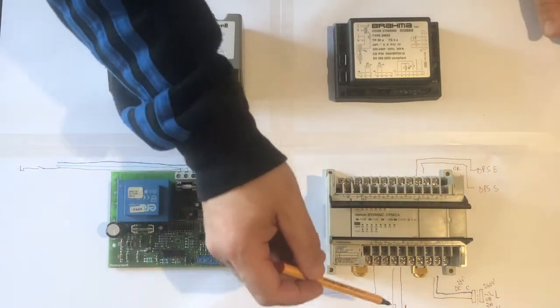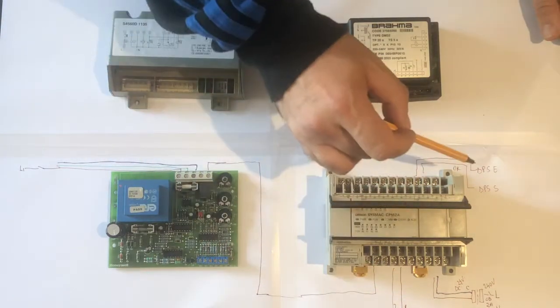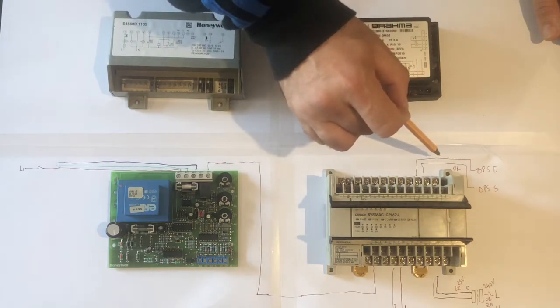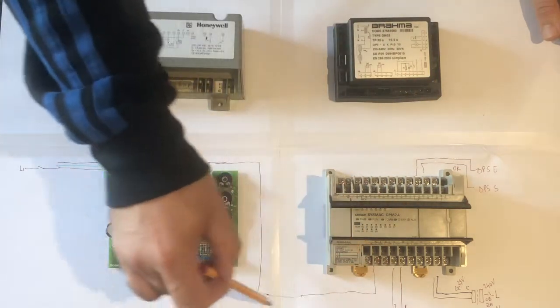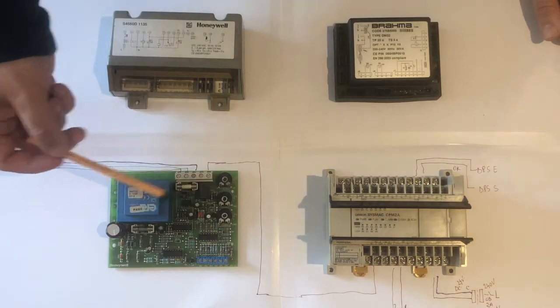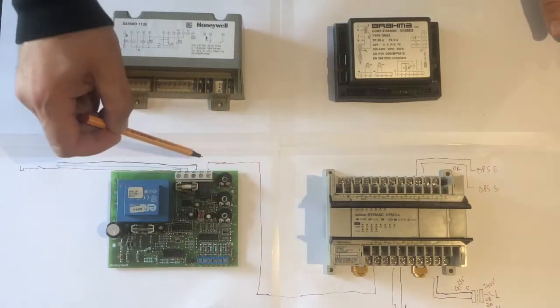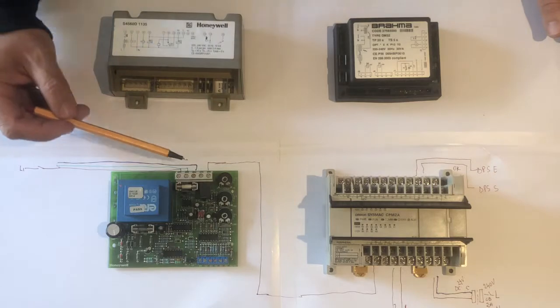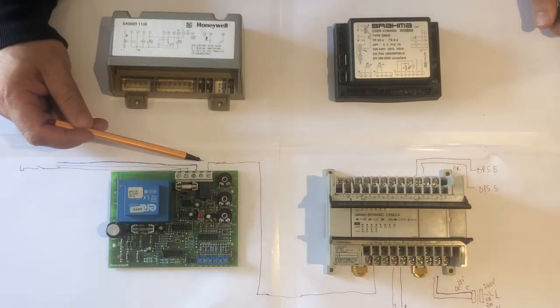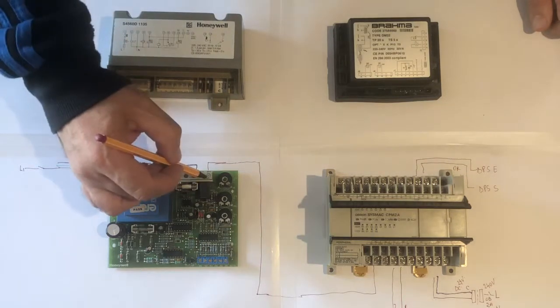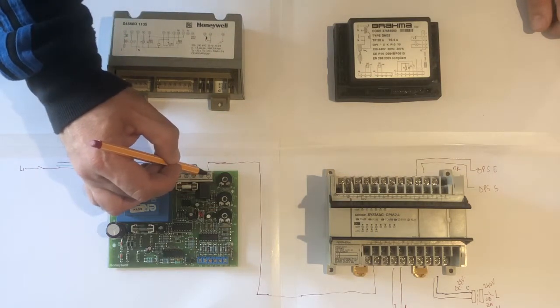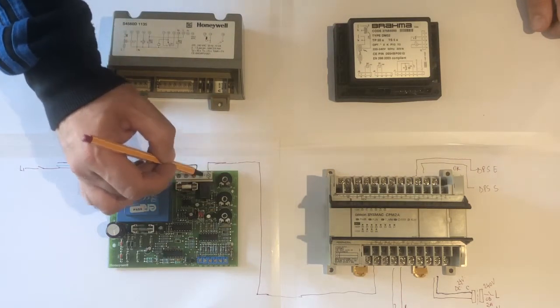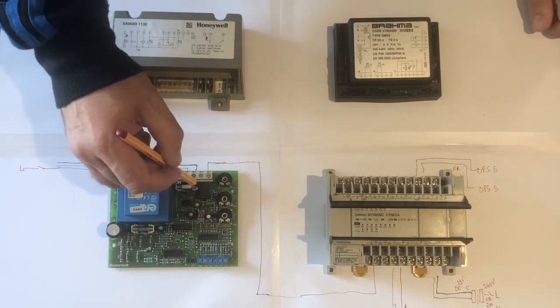So when the extractor fan and supply fan work, the differential pressure switch sends a signal that it's okay. A signal to this controller will be sent by the building management control to this relay, which is the output. I can't see very well, but I think it's 06, and it is this one. I want you to see it. I'll mark it up so you will see this one. So okay, our power supply comes here and it's interrupted by this relay.